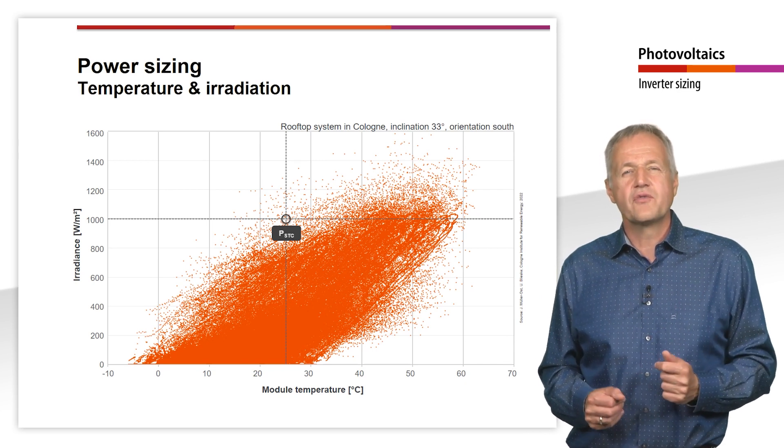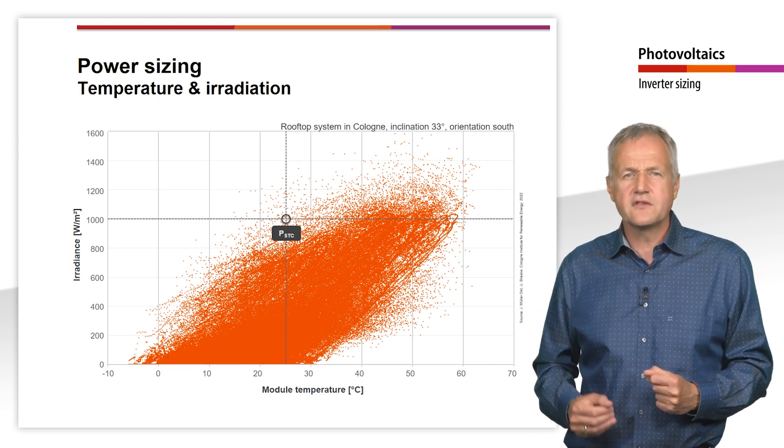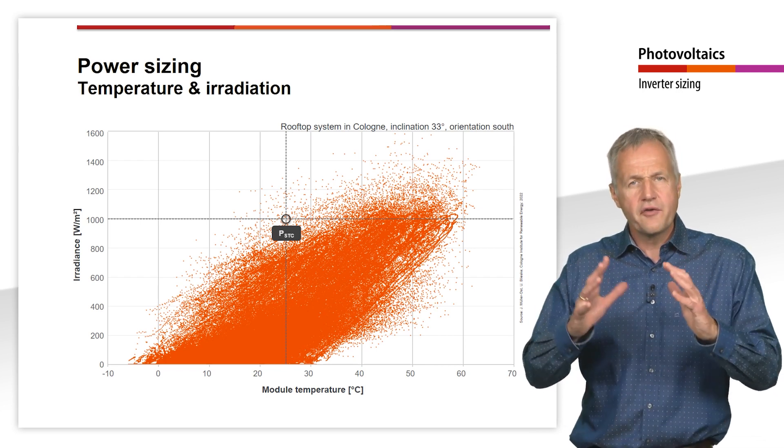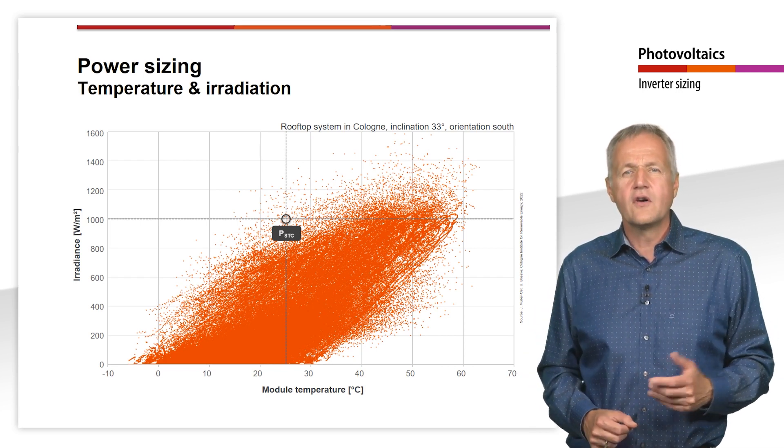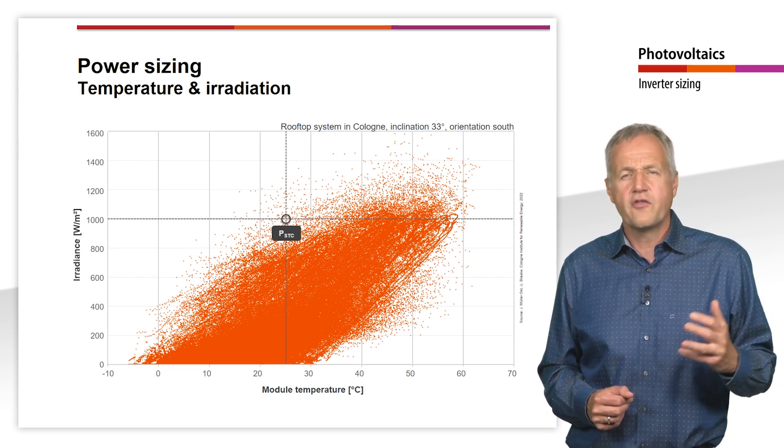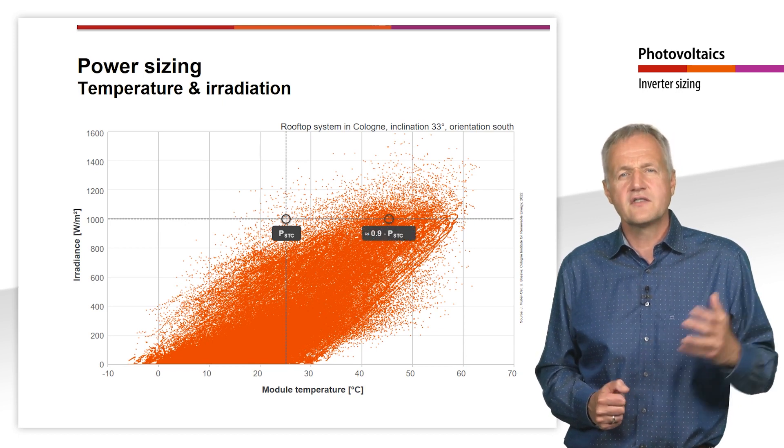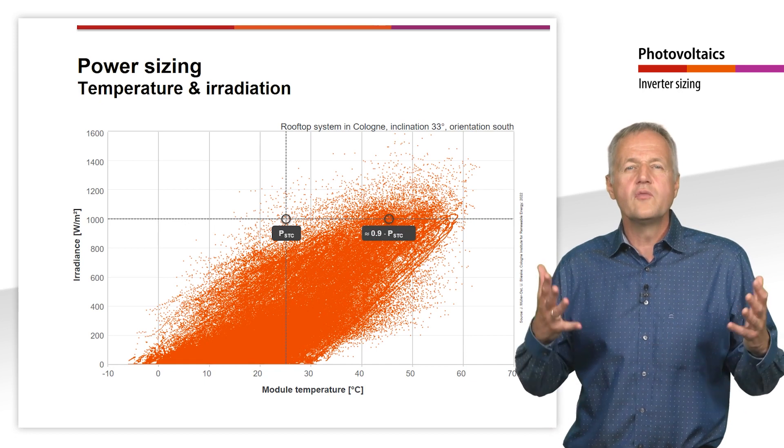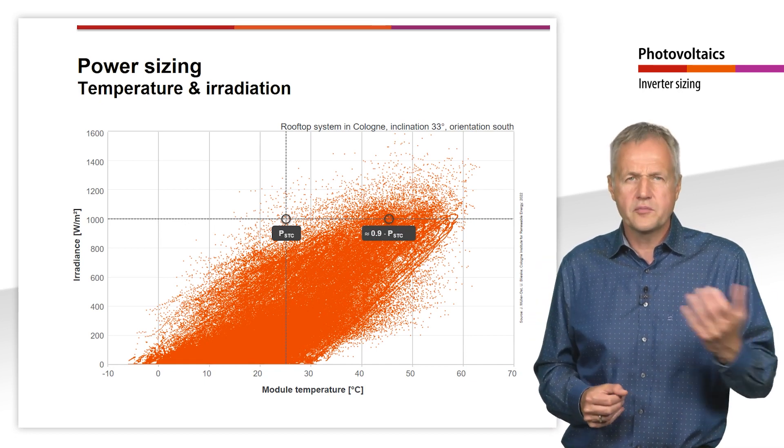When the temperature rises by 10 degrees Celsius, the output of an average silicon module decreases by around 5%. So, if the module temperature is at moderate 45 degrees Celsius instead of 25 degrees Celsius, we must already assume a 10% lower output.